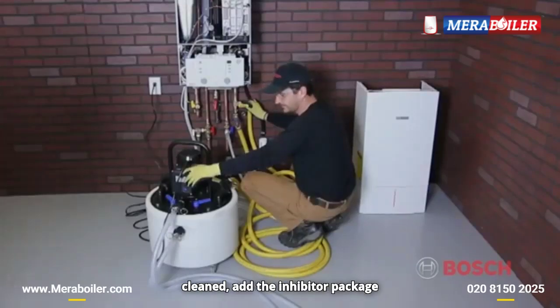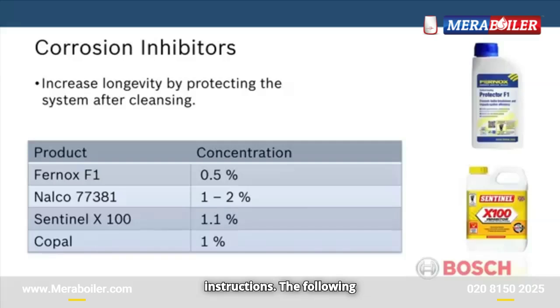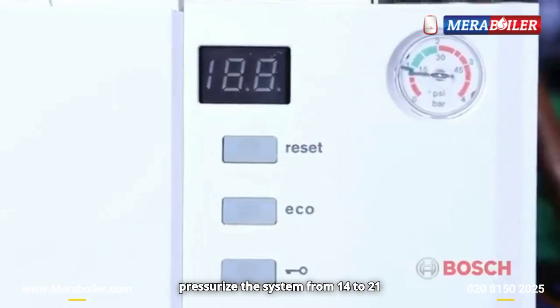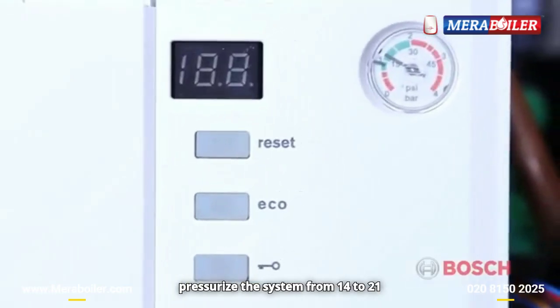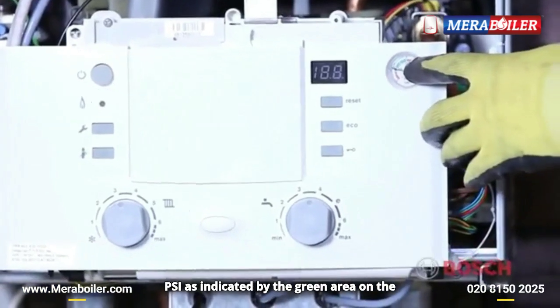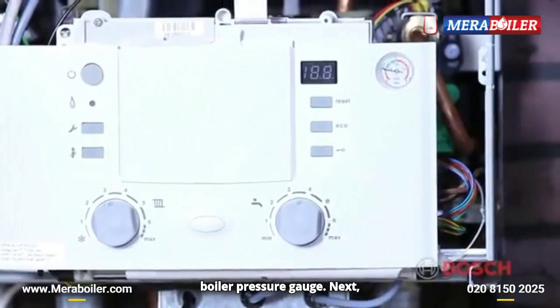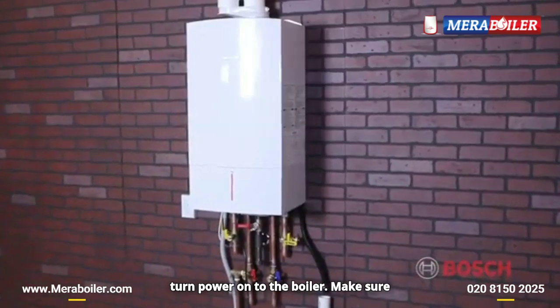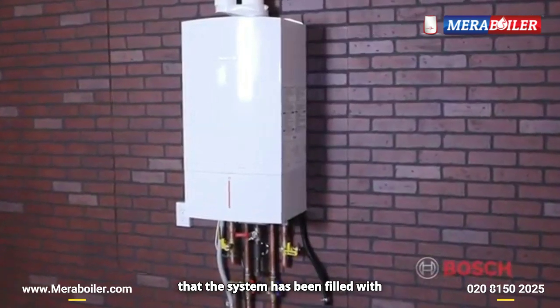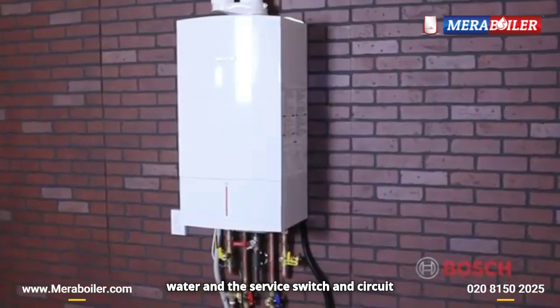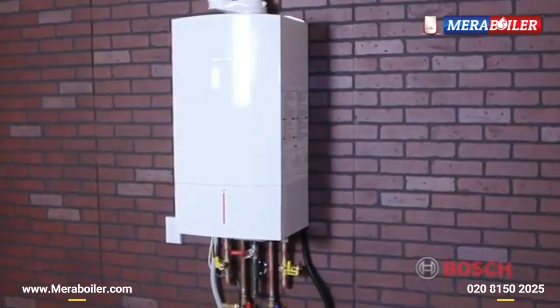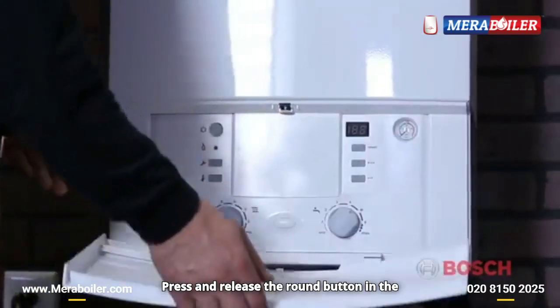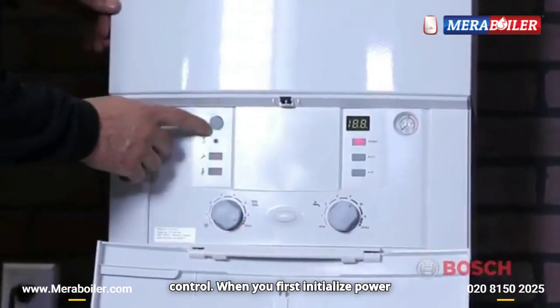Once the system has been cleaned, add the inhibitor package following the manufacturer's instructions. The following anti-corrosion inhibitors and concentrations are approved for use with the Greenstar boiler. Once finished, pressurize the system from 14 to 21 psi, as indicated by the green area on the boiler pressure gauge. Next, turn power onto the boiler. Make sure that the system has been filled with water and the service switch and circuit breakers are in the on position. Press and release the round button in the upper left-hand corner of the Heatronic control.